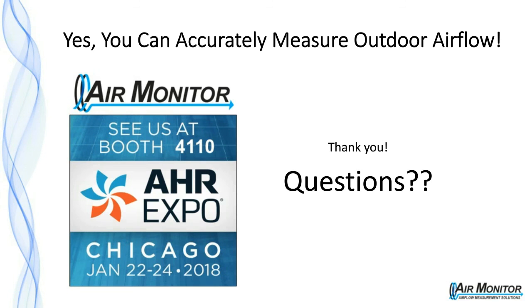Okay, another question along the same lines: is it beneficial to compare a calibration flow at both the design maximum and minimum airflows? We have to worry about the term calibration. The device can be calibrated at the factory provided the conditions are known at that time. But in the field, what we're doing is more or less a field commissioning or field validation. In our experience, if you can achieve that maximum and minimum design, the unit will allow you to put those values in so that you can have a very accurate measurement across that entire flow range. But again, that's based on something that's not meeting a calibration point for the meter.